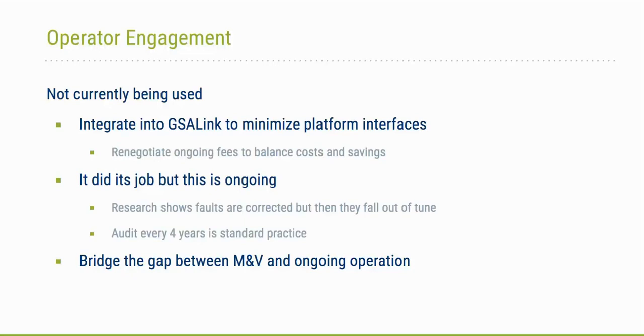With that said, too, we were able to identify some faults with how those CRAC units are operating. But with their O&Ms and how they tend to run our buildings, it's always good to have that ongoing verification, making sure equipment's not falling out of line. And then you've got that ongoing fault detection with these meters in place, which is an obvious benefit to keeping those versus installing them, finding your performance corrections, then moving on to the next spot.